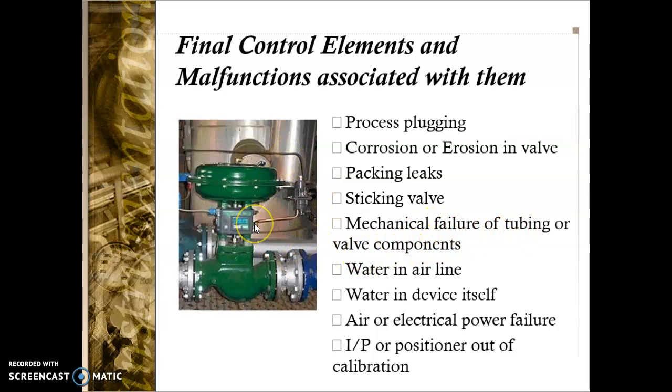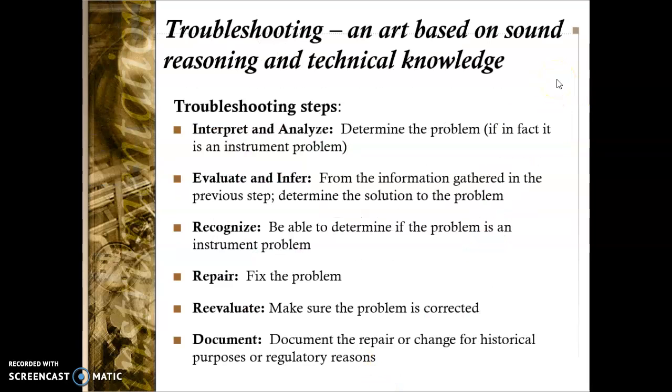Water in the airline, very bad. Water in the device itself. You could have air or electrical power failure. And then your I to P, your current to pneumatic signals, and or the positioners could be out of calibration. So they have to be looked at as well.